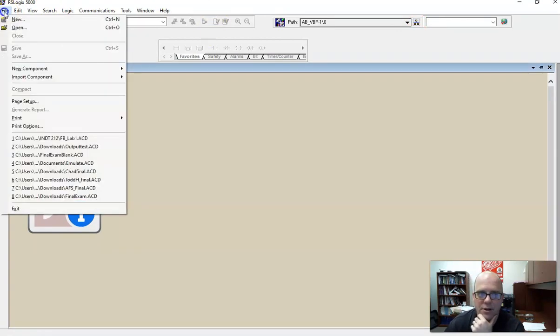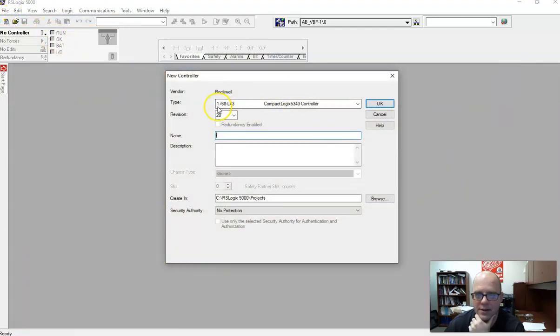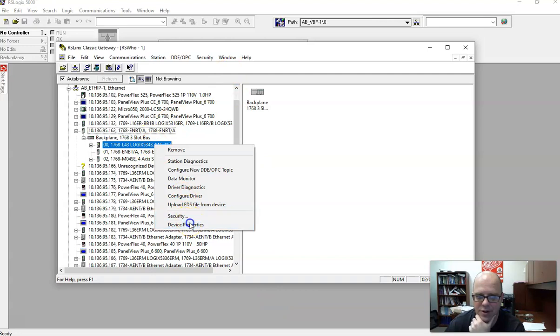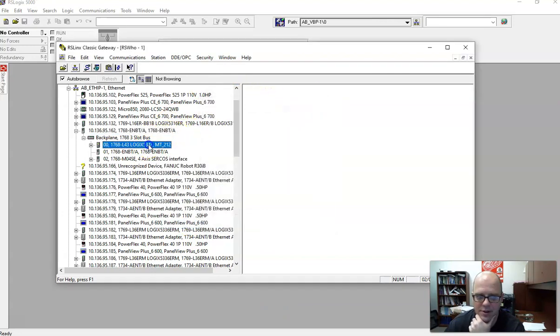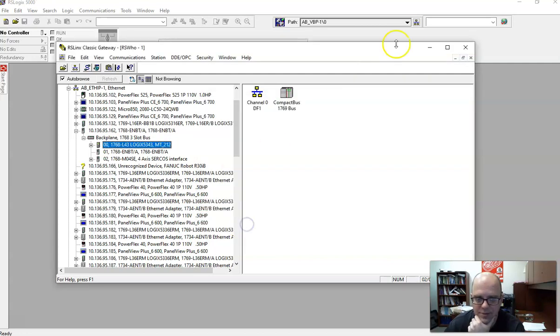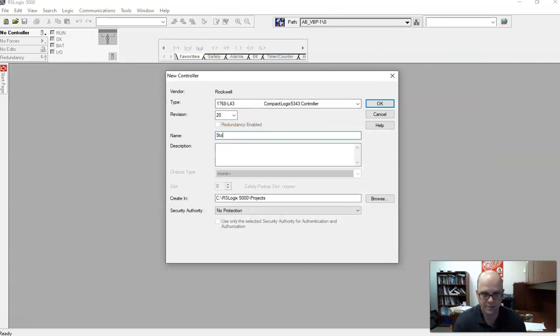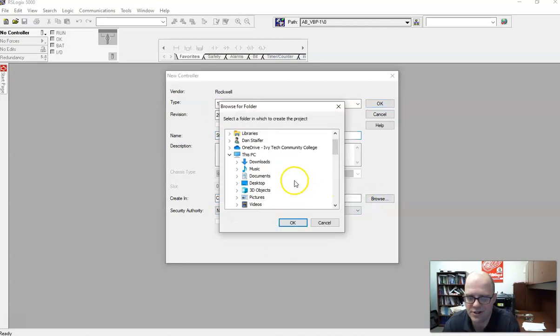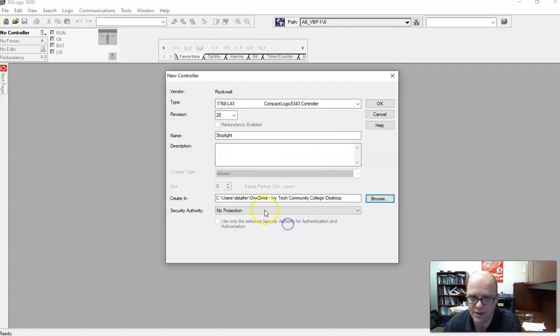Here's my program, and I want to do a new. And we have a 1769 L43 controller. If you didn't know that, you can look into RSLinx and right-click on the controller for device properties. So it's important that you set up your hardware properly. So for name, we'll do stoplight. And we want revision 20. We do not want any protection, and this is where you save it. Know where you save it. I would recommend changing this to your desktop so you can find it. Just from experience. So change that to the desktop and hit OK.